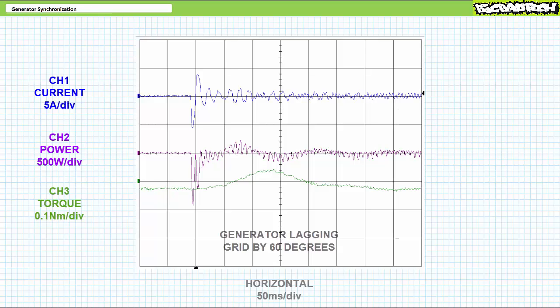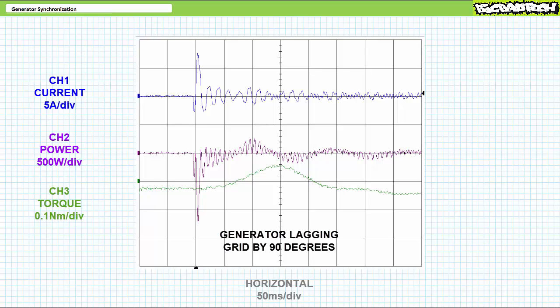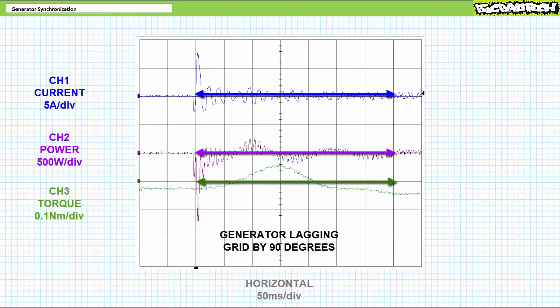Let's make it worse. Consider what happens when I close the contactor when the generator matches grid phase shift, frequency, and voltage magnitude, however the rotor is a full 90 degrees lagging behind the stator at the time of closure. This is bad. Electrically, there's a supermassive surge of current and electrical power into the machine, and mechanically, the shaft experiences a large surge of clockwise torque. The grid is yanking the lagging rotor forward as would a motor, only this time with a degree of viciousness. Besides increasing the magnitude of the electrical and mechanical transients, greater and greater mismatches also result in longer durations of undesirable electrical and mechanical transients.